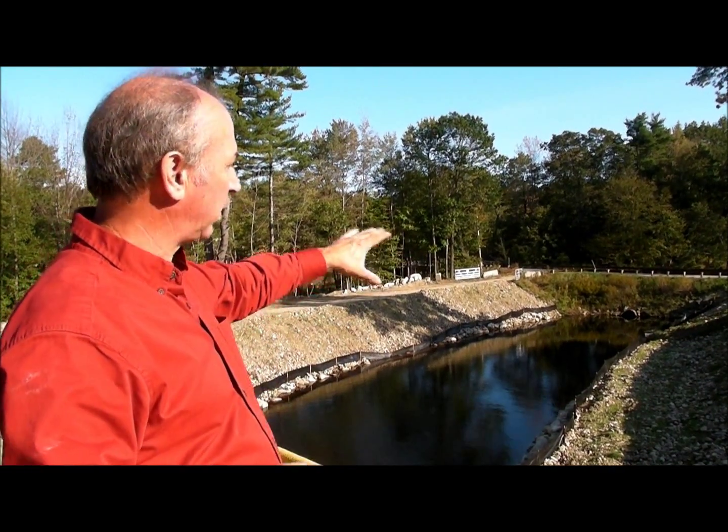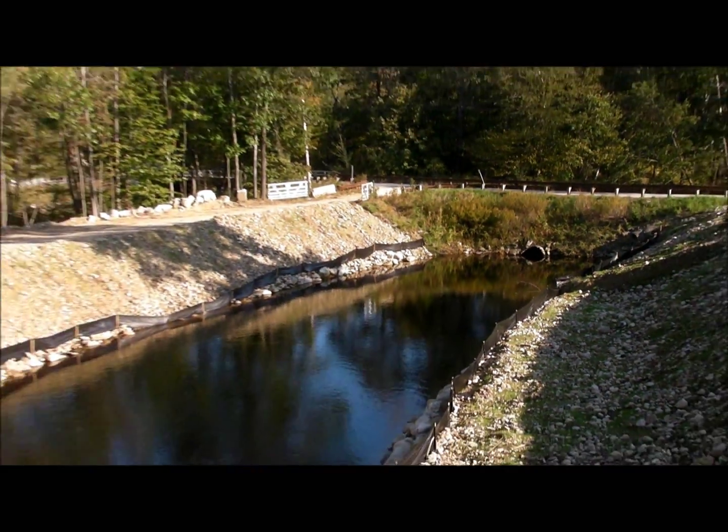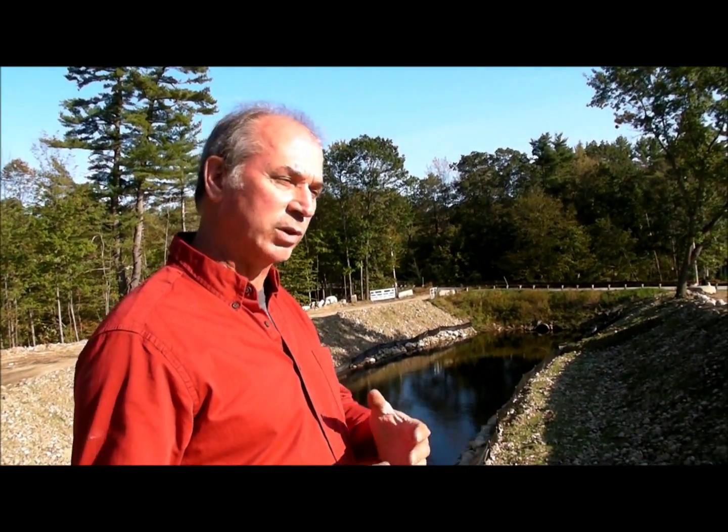Our project is to replace that small metal culvert with big concrete box culverts, which will restore the water flow back to what it should be and increase our electricity production by 17%. That 3-foot difference in head pressure can mean hundreds of thousands of kilowatts of electricity not generated simply because of the culvert backing up the water. By replacing it, we'll restore proper water flow, drop the tailrace down another 3 feet back to original design, and generate electricity at full capacity. Once we put those culverts in, they'll last 100 years — no maintenance or upkeep required.